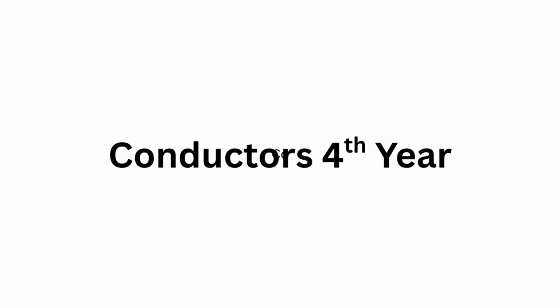You nailed it. And that third point, the termination temperature, that's often the biggest limiting factor. It's all about protecting the connection points, the weakest link, really. See, the current listed in those key tables 1 to 4, that's the maximum current that'll make the conductor hit that specific temperature. Okay. So you can't just pick the highest rating the wire itself can handle. Exactly. You have to look at the lowest temperature rating of any piece of equipment that conductor connects to. Usually that's 75 degrees C or maybe 60 degrees C.